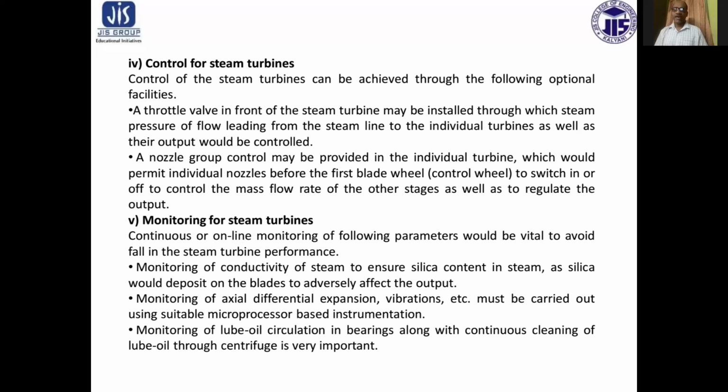Monitoring of axial differential expansion, vibration, etc. must be carried out using suitable microprocessor based instrumentation. Monitoring of lube oil circulation in bearing along with continuous cleaning of lube oil through centrifuge is very important.